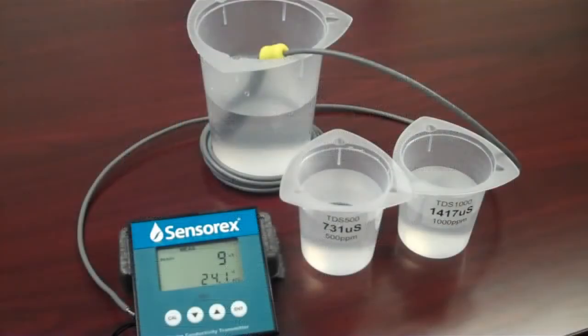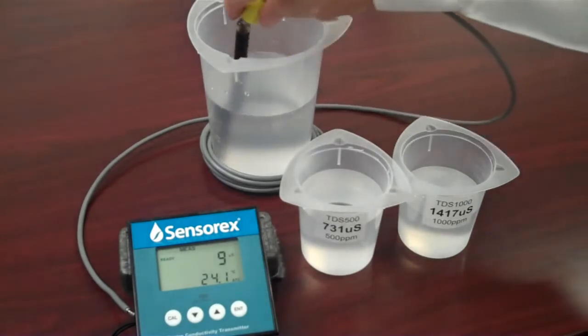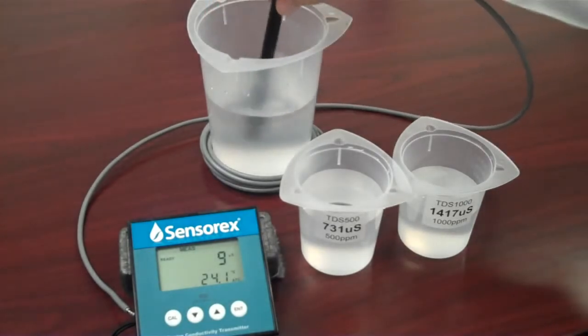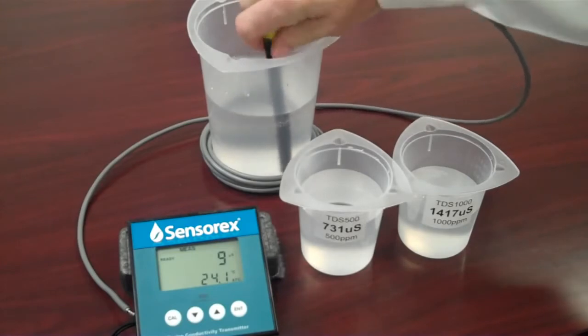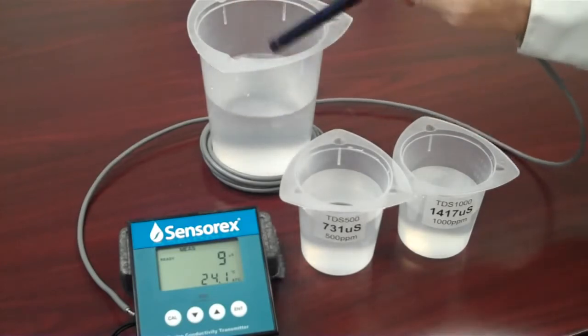For best results, select the conductivity standard solution that is close to the sample value you expect to measure. If you'll measure over a large range, select a standard that's about 65% of your full-scale range. For our example today, we will perform a single-point calibration. Place the conductivity sensor into a container of clean rinse water. Use deionized water or distilled water if it's available for critical applications.